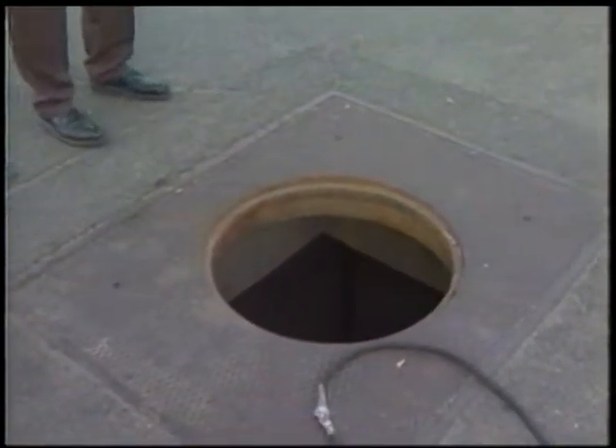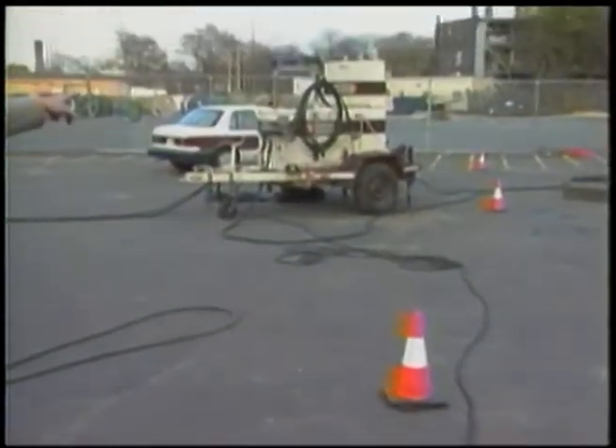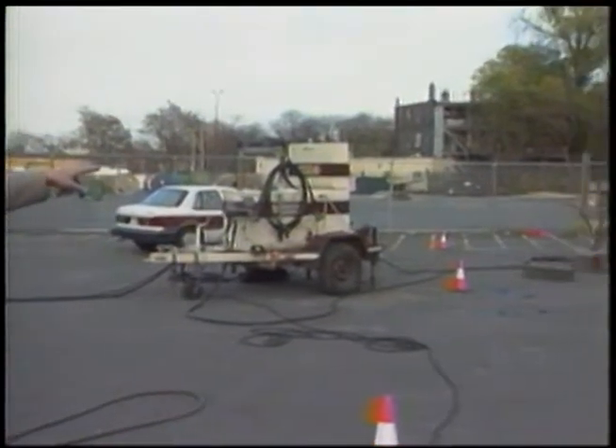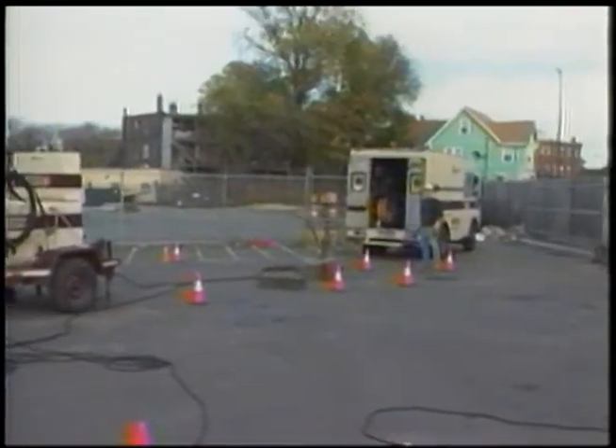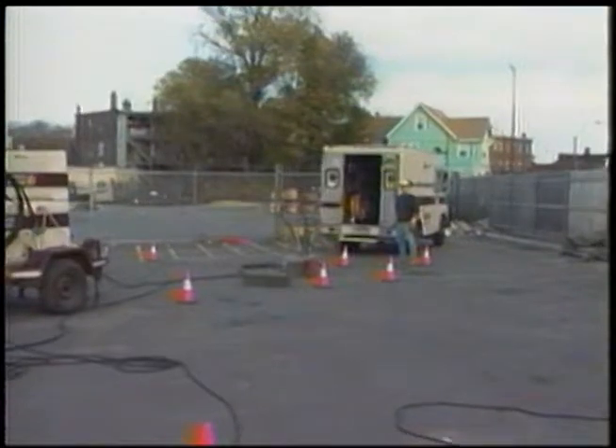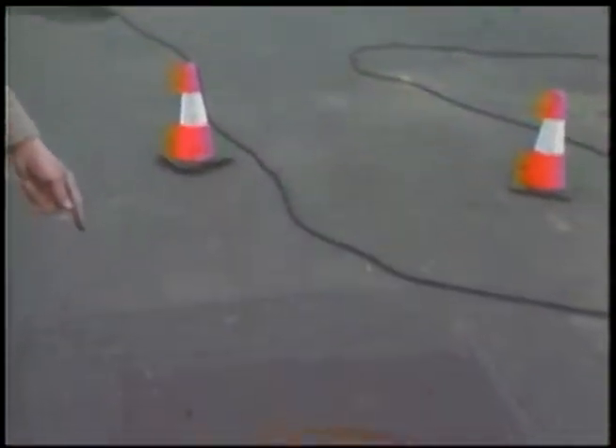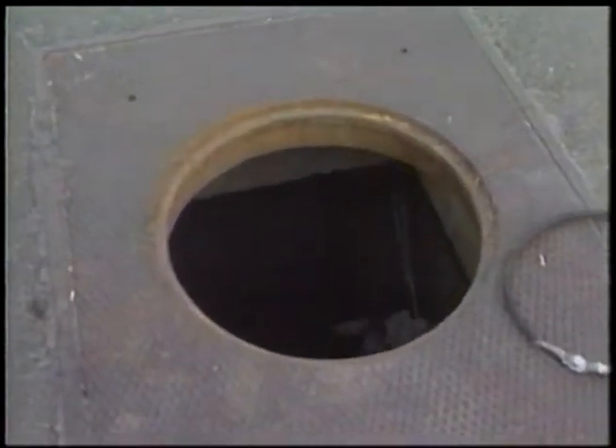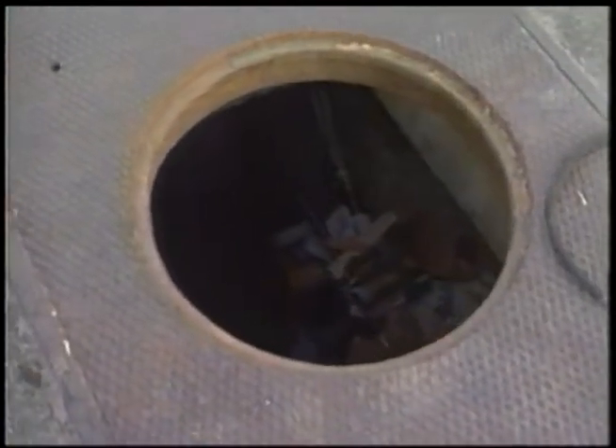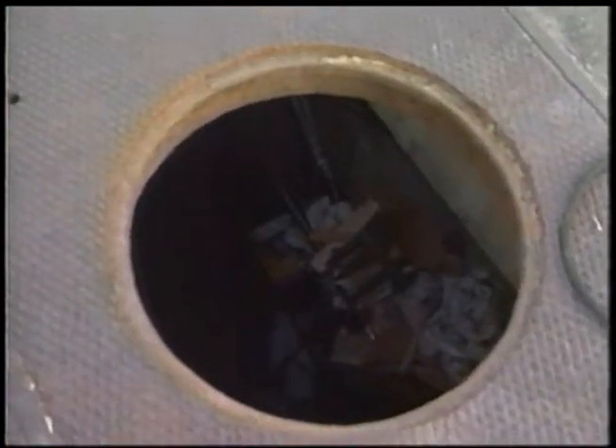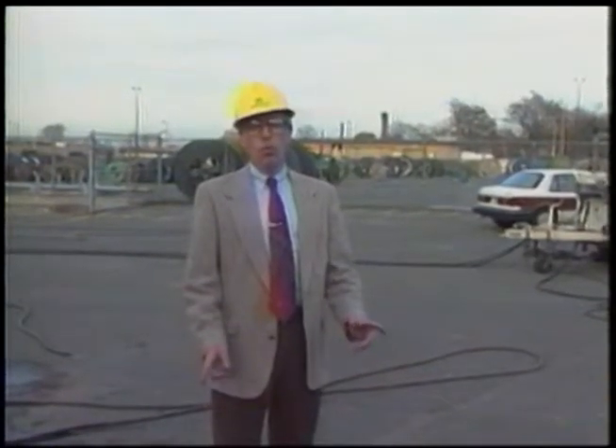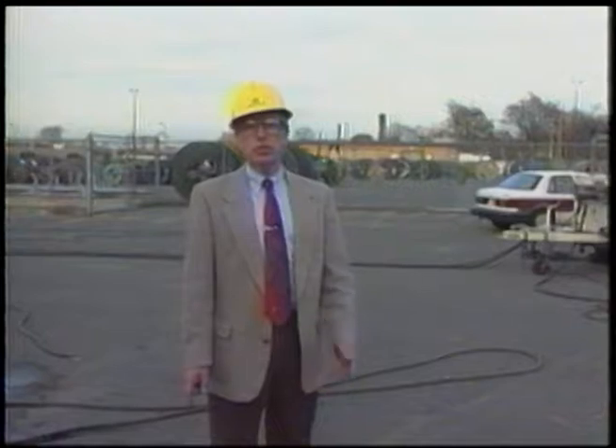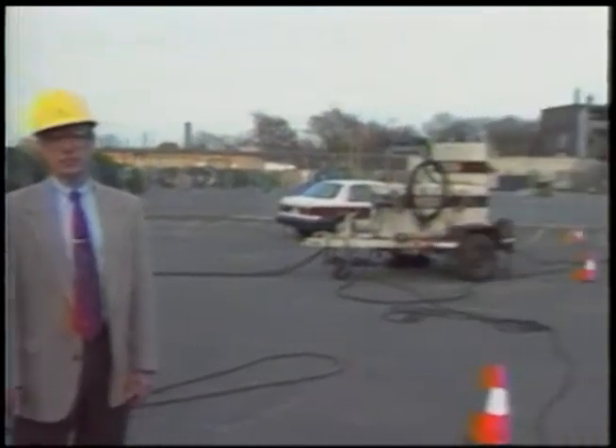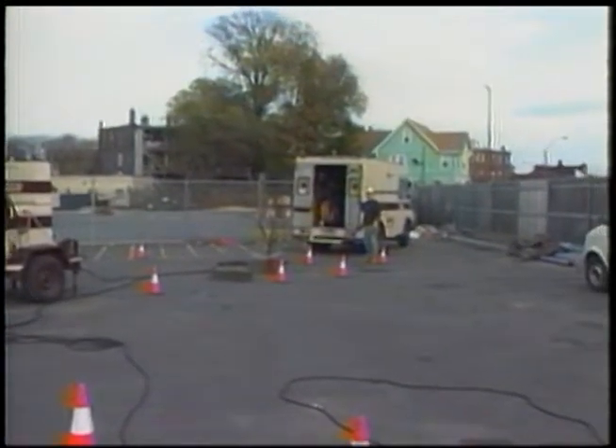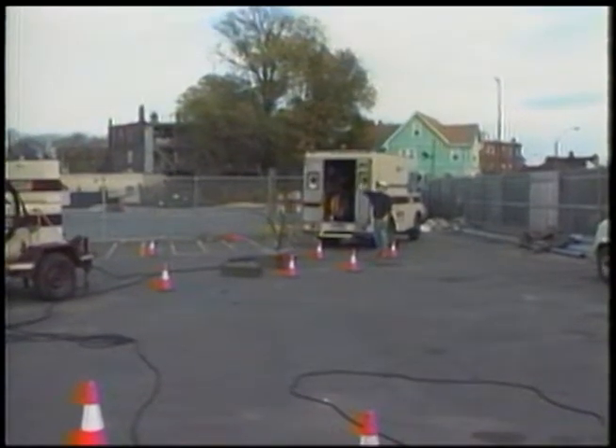We're going to take the transformer that we've used already to energize the high voltage cable. We've connected it to another high voltage cable in the adjacent manhole. We're running that high voltage cable into this duct so we can energize the fault. When the cable gets energized, the fault inside the manhole will set the debris on fire. When the fire is going, I will approach the manhole with water coming from a garden hose to put out the fire. Dennis, energize.